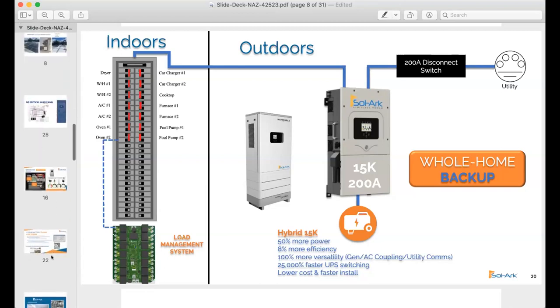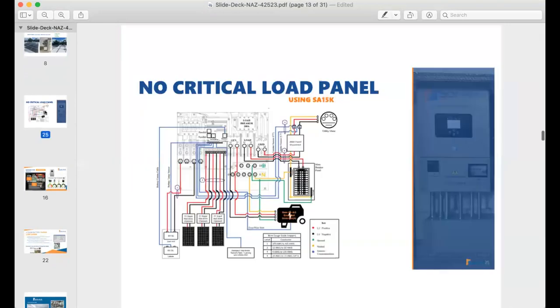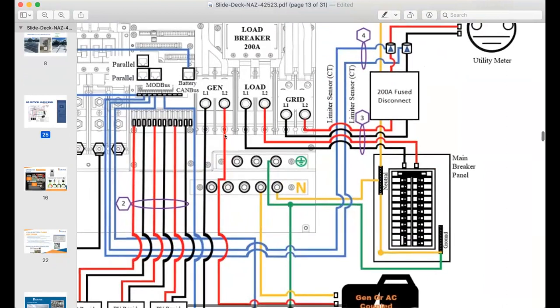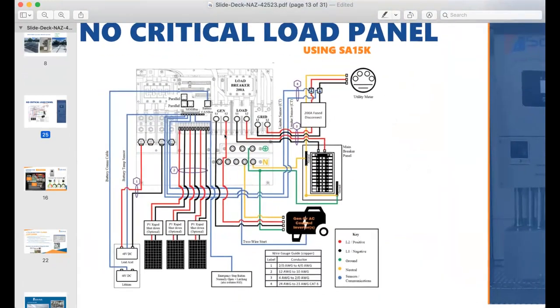The Sol-Ark also has some cool features on the gen side. In my application I don't have a generator, so I use that circuit as a dump load circuit — it goes and powers supplemental air conditioners, baseboard heaters, and an EV charger. It has 50-amp output, so it can power quite a lot. These kinds of noncritical loads go on this circuit, and if the grid fails, it can shut those loads off. So even with just the Sol-Ark itself, you have a lot of flexibility.